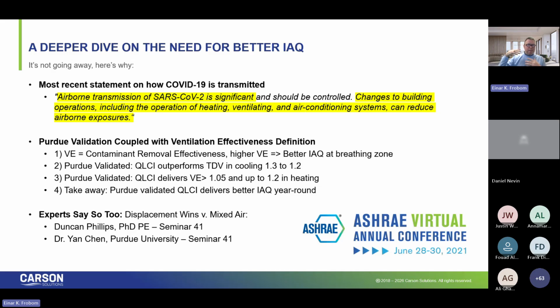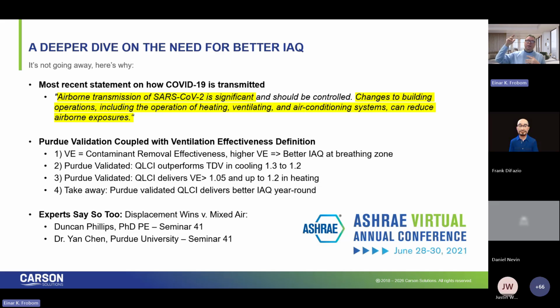So we created unity. Conversely, in that same operation in heating, it's typically assigned a 1.0. I'm sorry, 0.8. That's because as the air comes out of a ceiling diffuser, it's warm, it's buoyant, it doesn't want to drop, and the first thing it finds is the negative pressure relationship of the exhaust or return air grille. That ends up being 1,000 parts per million of CO2, and where the students are is 1150. So that system has created a better air quality going out than where the students are. And our industry's response is to simply increase the amount of outside air in our mixed air rooftop or air handler. Just because you add more air at the air handler doesn't in any way, shape, or form guarantee that fresh air is going to get to the students, particularly in heating.